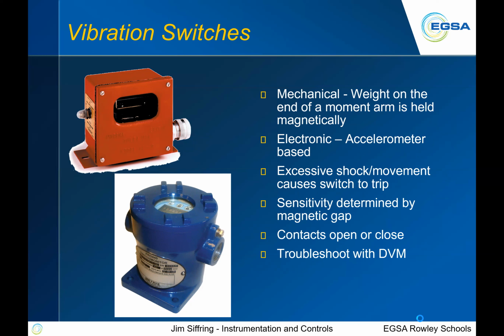Then we move into the lower graphic with the blue device. It'll still do that shock sensing, but it also gives us all kinds of other input, such as vibration and knock sensing and things such as that. A lot of times all they do is open or close a contact. It may not even give you any kind of live data out. All it is doing is looking at what kind of impact has happened. Or you might have them that are more comprehensive and give you a signal out.